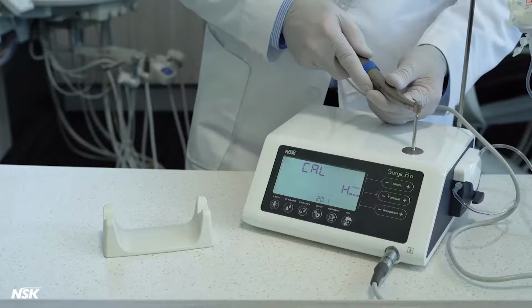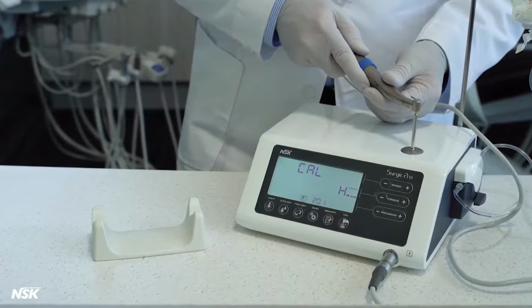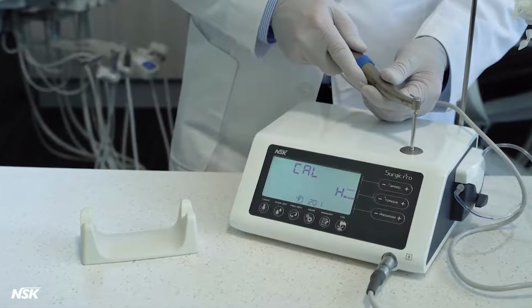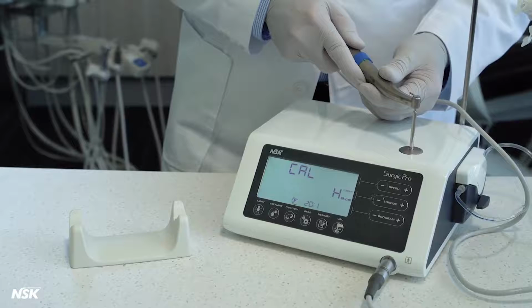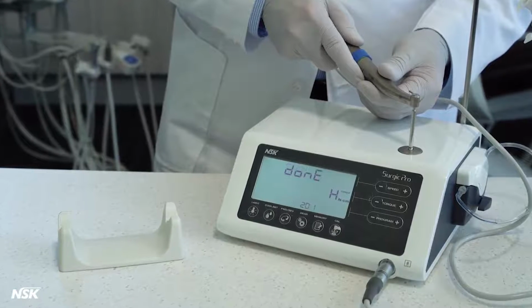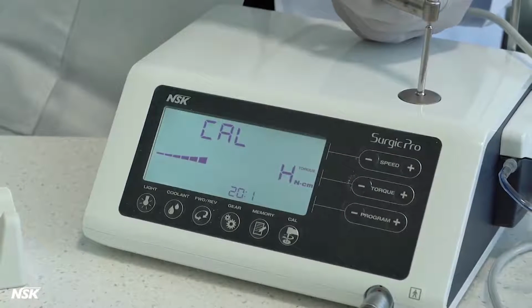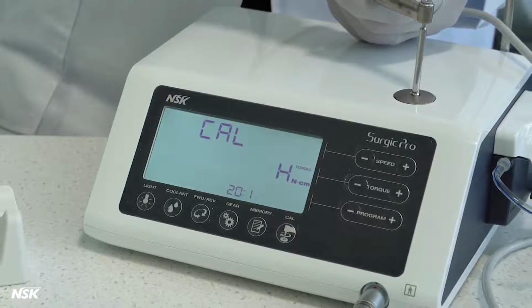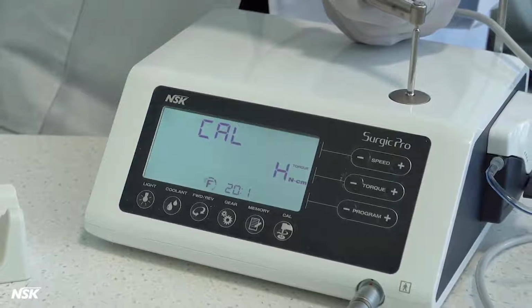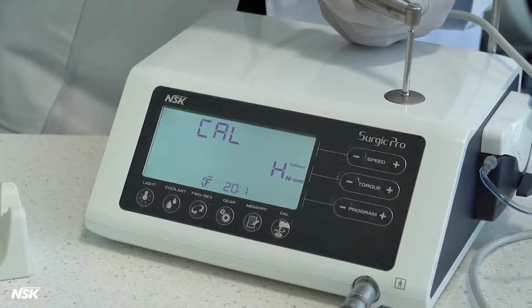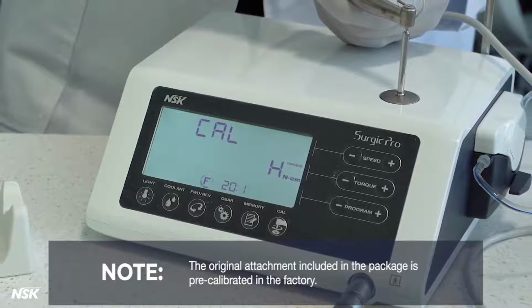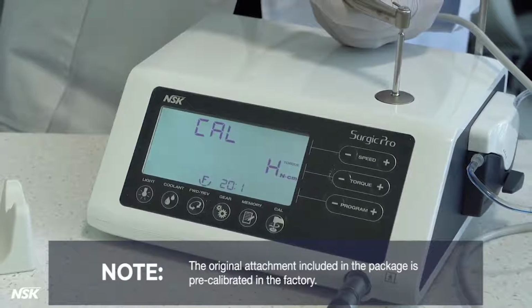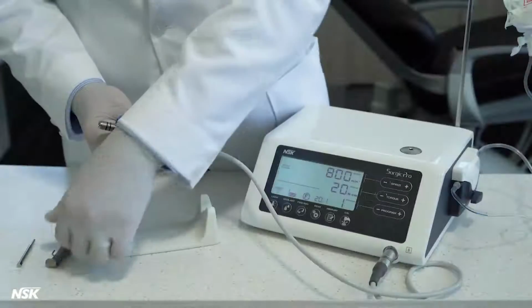Calibration. Calibration is aligning the specs of an implant attachment with the control unit to make sure there's the correct amount of speed and torque being delivered through the attachment to the drill. As implant attachments age through normal wear and tear, or when you want to use a new attachment with the motor, you'll need to perform calibration. Note: the original attachment included in the package is pre-calibrated in the factory. Here's how you do it.